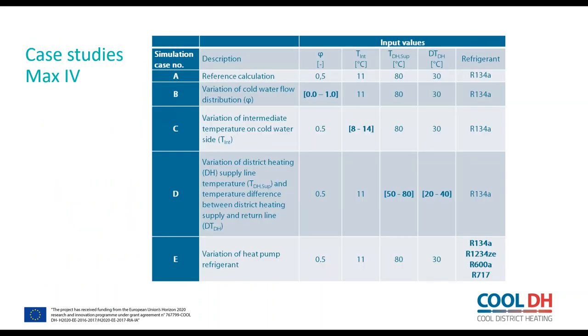So I would just go forward to look at the parameter studies. And this was the case at Max 4, where, as I said, we varied the parameters, the internal flow distribution, we varied the inlet temperature, and we varied the supply and return temperature to the heating grids. And also the refrigerant was varied. So all these studies were made to find the optimal in each case.